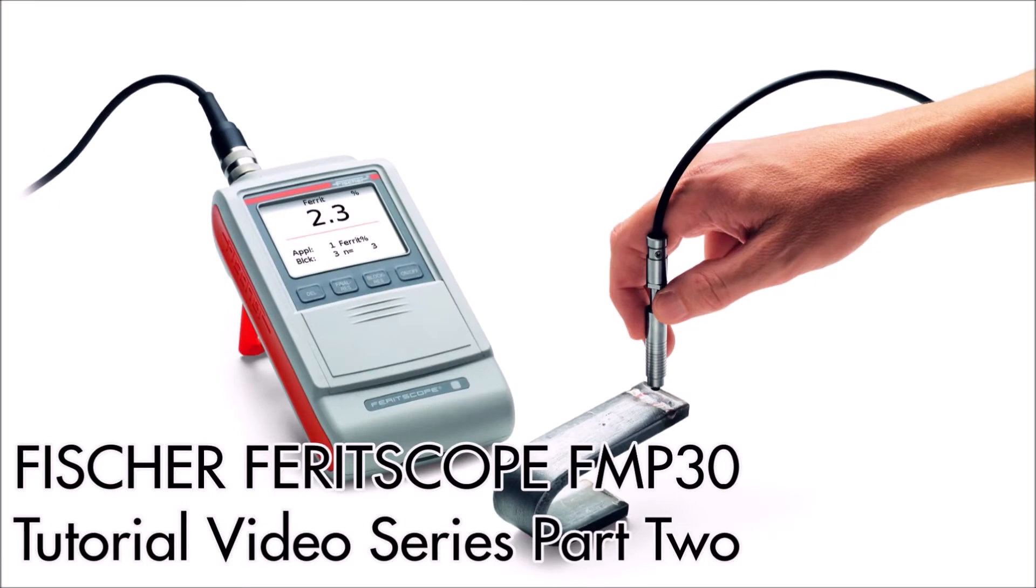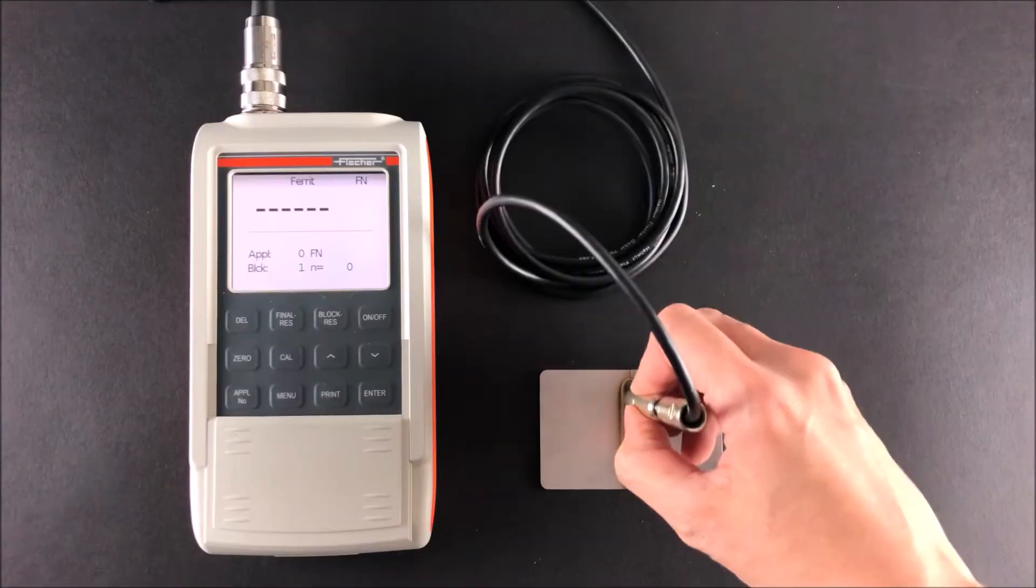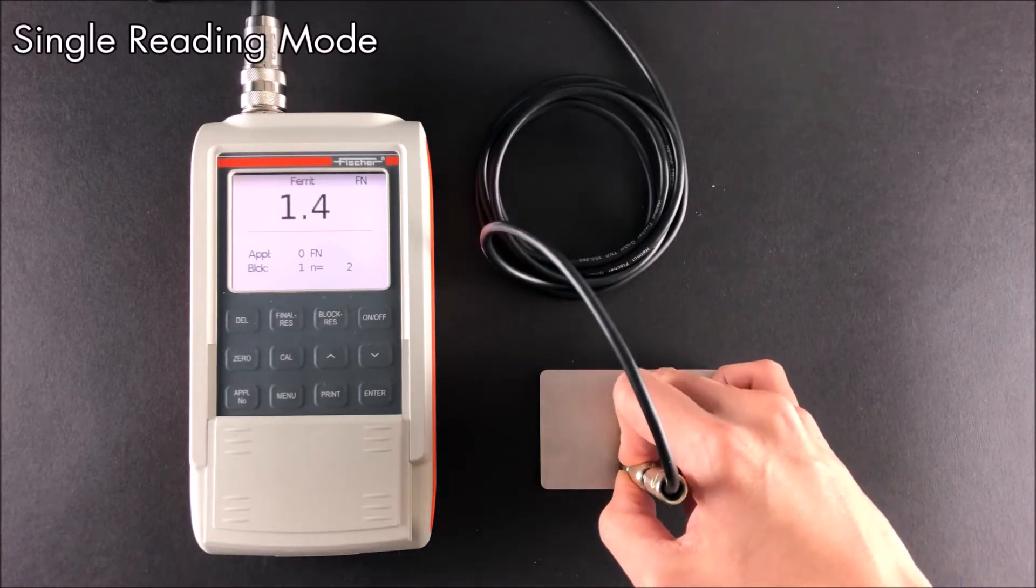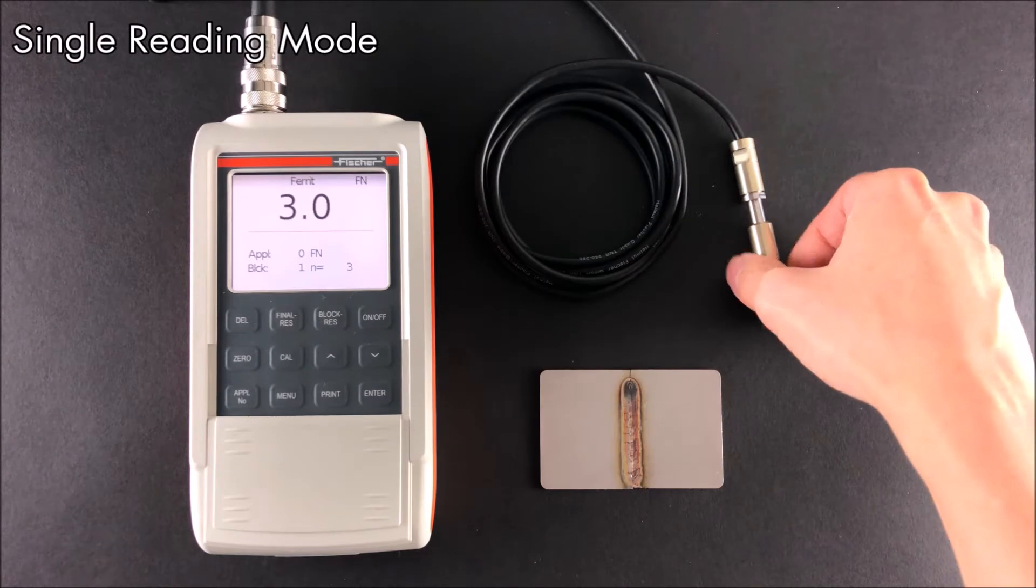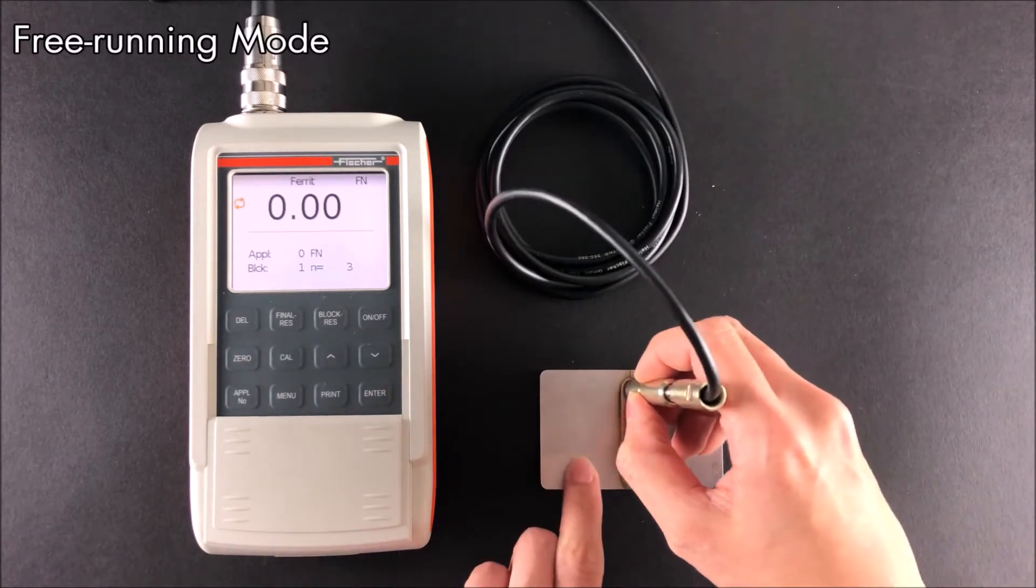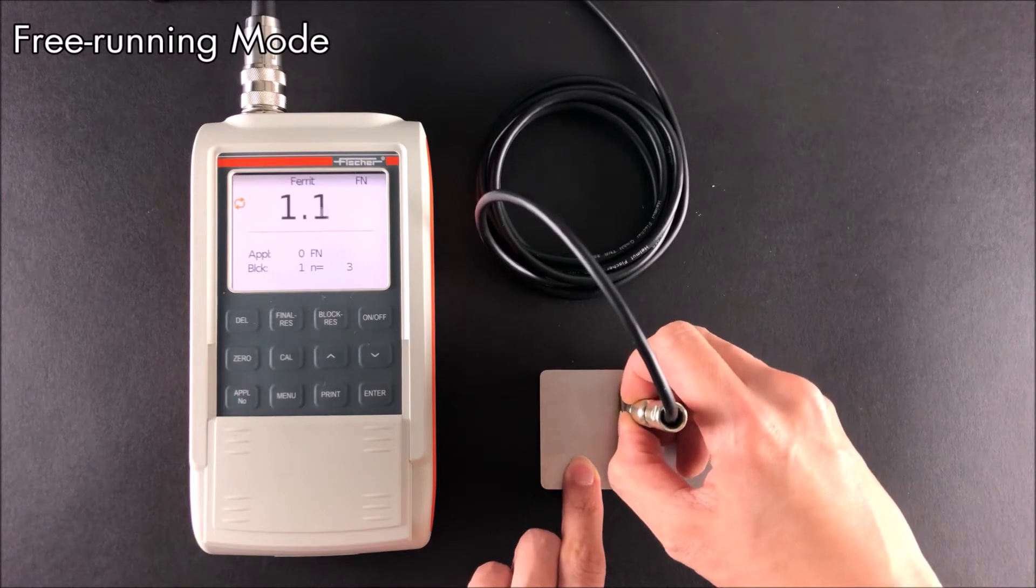Welcome to part 2 of the Feritscope tutorial video series. There are two forms of measurement modes available, including single reading mode, which takes a reading each time the probe is in contact with the surface, and free running mode for continuous scanning of surfaces.